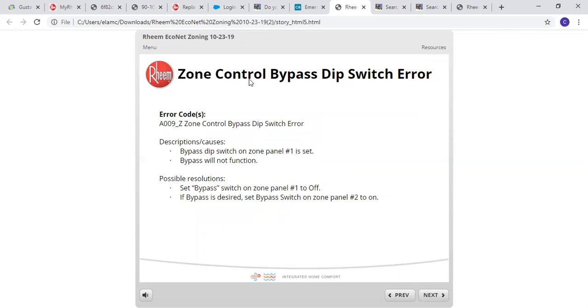This one's zone control bypass dip switch error, A009. So some descriptions or causes here: bypass dip switch on zone panel 1 is set. Bypass will not function. So if you're using one board and you have your dip switches turned on for whatever reason, you will get this fault code. Possible resolutions: set bypass switch on zone panel 1 to off. If bypass is desired, set bypass switch on zone panel 2 to on.